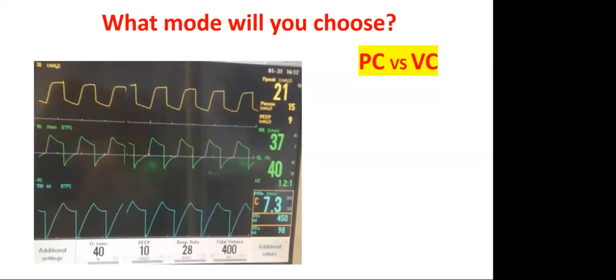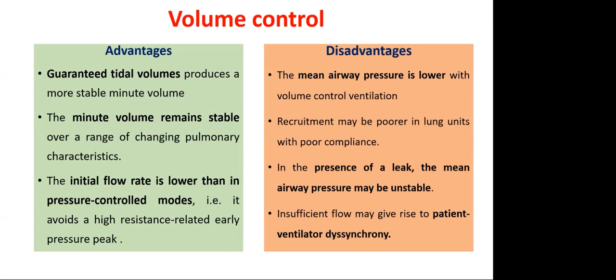So what are the advantages of each mode? Volume control mode, as I already mentioned, gives guaranteed tidal volume and minute volume, and will be stable. The only disadvantage is, in the presence of leak, the mean airway pressure is unstable, and sometimes with insufficient flow they may have patient-ventilator dyssynchrony, and especially with poor compliance lung units, the mean airway pressure will be lower. So always remember, if you're ventilating a child with normal lungs, like a post-op child, you can put on volume control mode. Otherwise, if the child has diseased lung with poor compliance, try to put on pressure control.